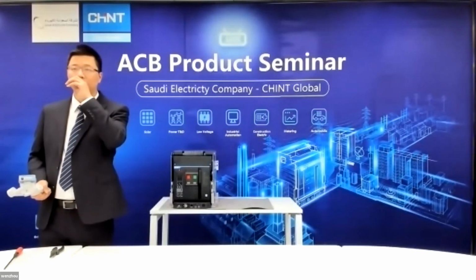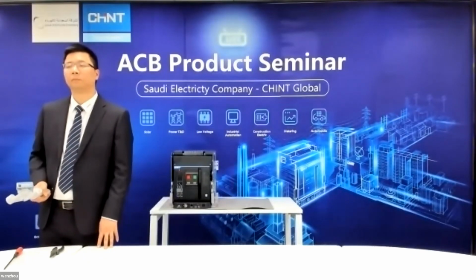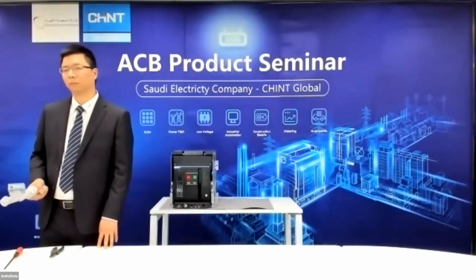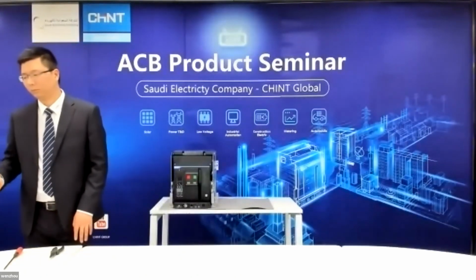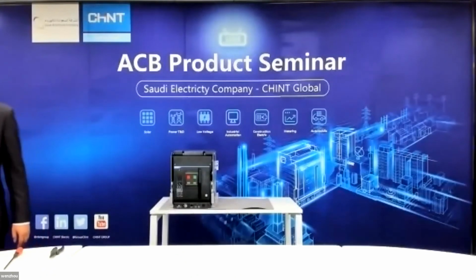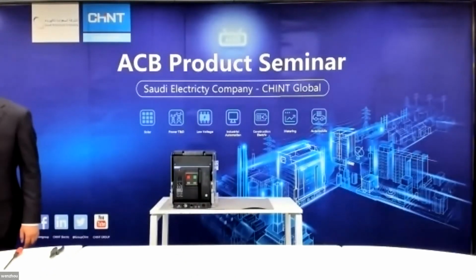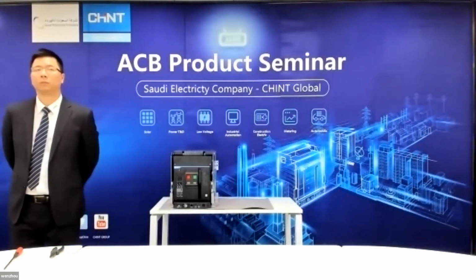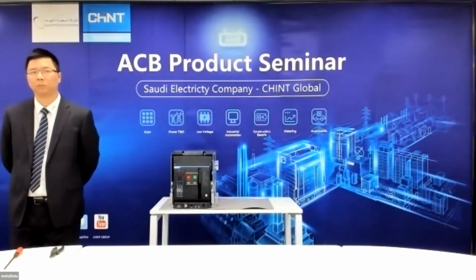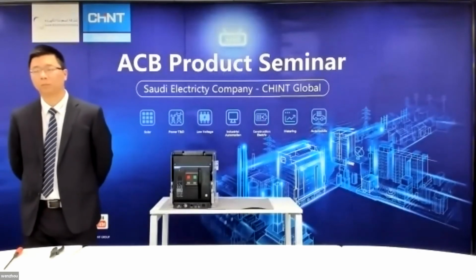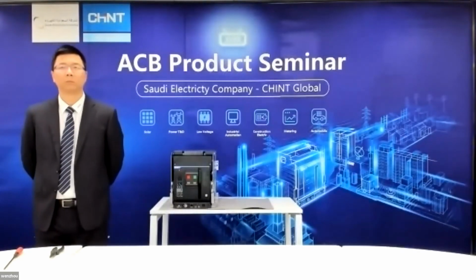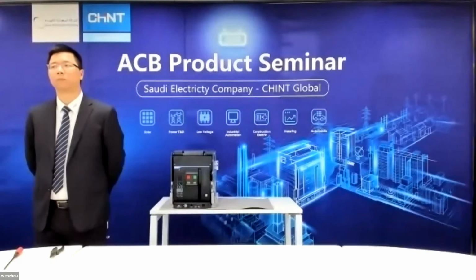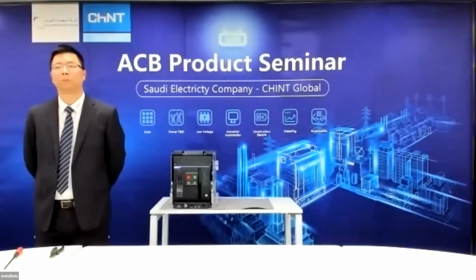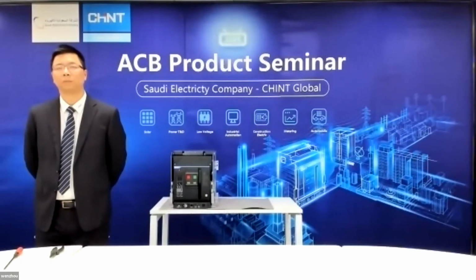With respect to our protection unit, the logic control unit, there are built-in differential coils which can be configured to distinguish between earth leakage and harmonics, by identifying the type of harmonic - first, second, third, or fifth. So there's a possibility to distinguish between the earth fault or ground fault and the type of harmonic through our control unit. There are two coils, called the two differential coils, which can distinguish between these two types of currents, or sensitivity.